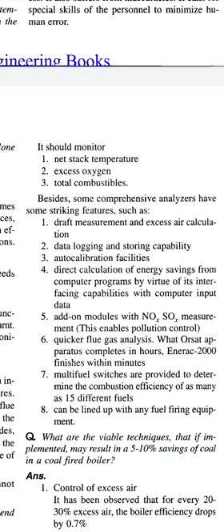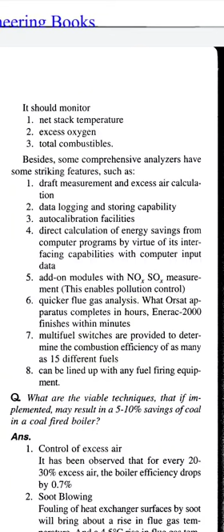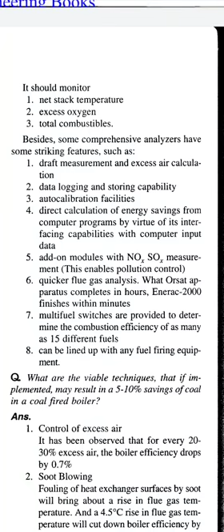It should monitor net stack temperature, excess oxygen, total combustibles. Besides, some comprehensive analyzers have striking features such as draft measurement and excess air calculation, data logging and storing capability, auto calibration facilities, direct calculation of energy savings from computer programs by virtue of its interfacing capabilities with computer input data, add-on modules with NOx, SOx measurement.